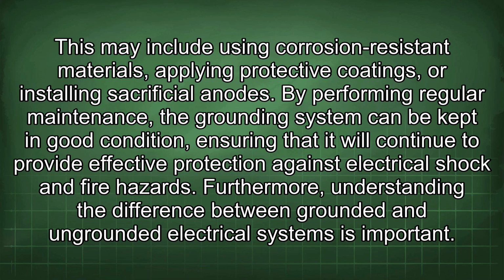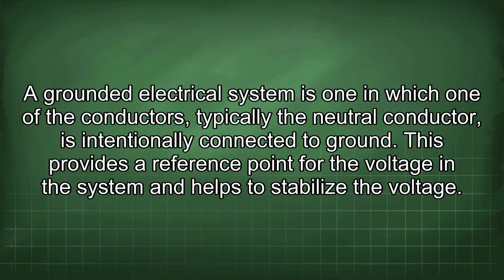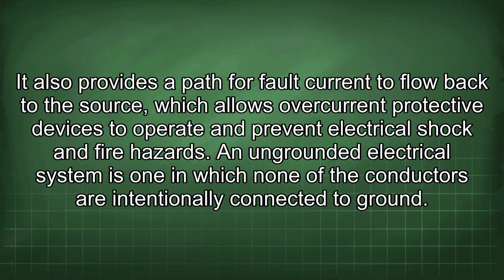Furthermore, understanding the difference between grounded and ungrounded electrical systems is important. A grounded electrical system is one in which one of the conductors, typically the neutral conductor, is intentionally connected to ground. This provides a reference point for the voltage in the system and helps to stabilize the voltage. It also provides a path for fault current to flow back to the source, which allows overcurrent protective devices to operate and prevent electrical shock and fire hazards.